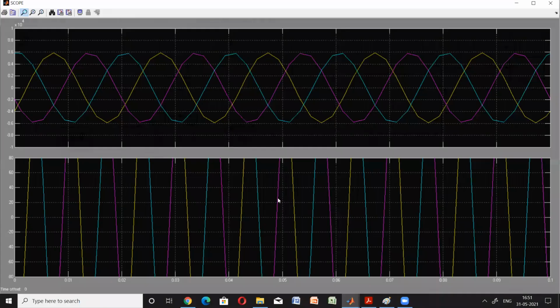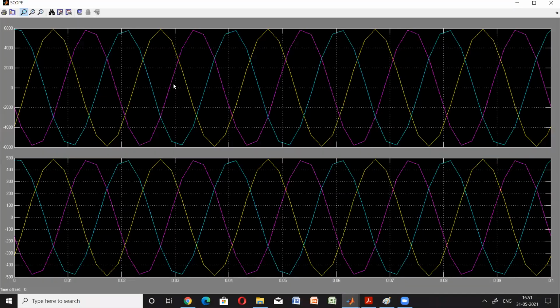As you can see, the current is extremely high. On the other hand, the voltage is going downward. The current is increasing at a very faster rate. Now the current peak value is around 500 amperes. But on the other hand, the voltage is decaying. Initially we had around 10 kV, then 9 kV, then 8 kV. Now we have around 6 kV of voltage.